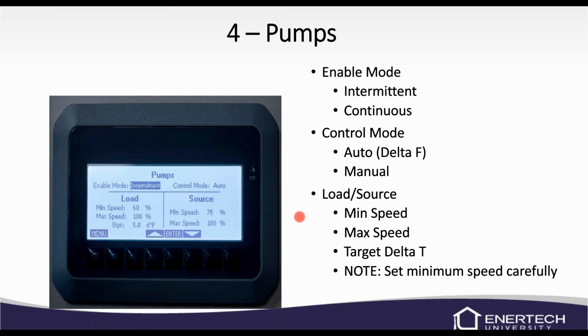Pumps menu, you can go into this menu here if you want to run your pumps, if you've had to reflush or replace a pump, or you want to set it up and run the pump to see what's going on. You can go in here and enable it to either intermittent or continuous, and auto or manual control mode. Auto is delta T. Manual is you're manually going to set it at a speed and let it run and see what happens. So it'll show you your minimum speed, maximum speed, and target delta T as well.